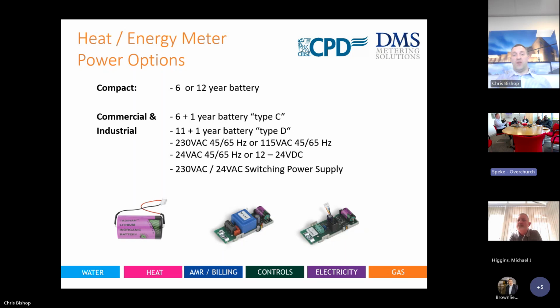Again, just to give you some visual on what a power supply looks like in a meter, if you're mechanically biased or electrically biased or a bit of both. Compacts, the standard that we still see quite a lot, which is quite surprising, but we try and guide people not to do it, is batteries. So batteries, fine, great. Cost saving to start with. You install a heat meter, you don't have to invest in a spur, an electrician, 3-core cable to actually get the power to that location. But the worst will happen because the battery at some point will die.